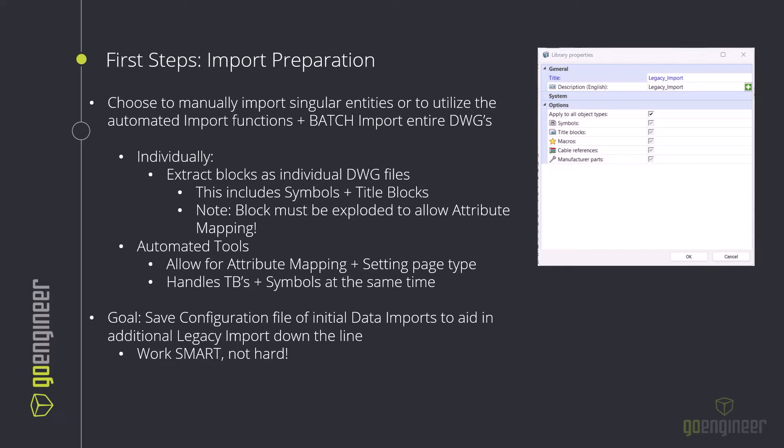Most people coming from a legacy software like AutoCAD Electrical need to ensure consistent attributes for description and part number across all engineers. That way, if a symbol is created by different individuals, it's still set up the same in the background and the software can automatically import it. For the individual method, we need to take every block, extract it to a DWG, and also explode that block — it can't be a block entity; we need it broken down into geometry and block attributes.